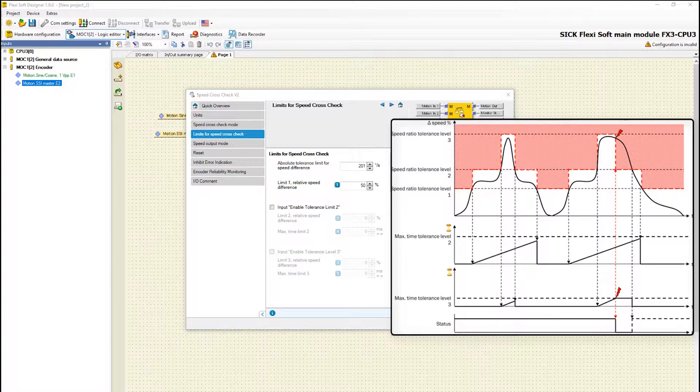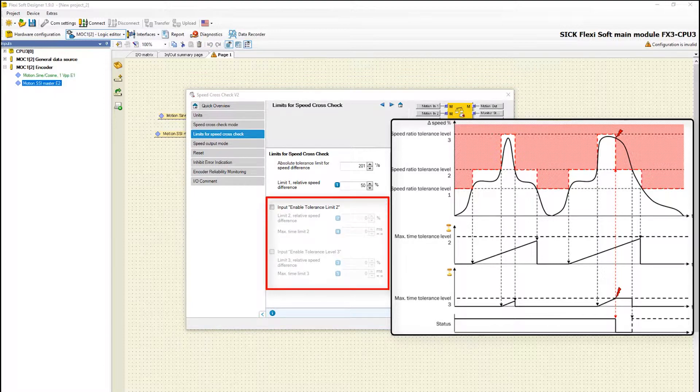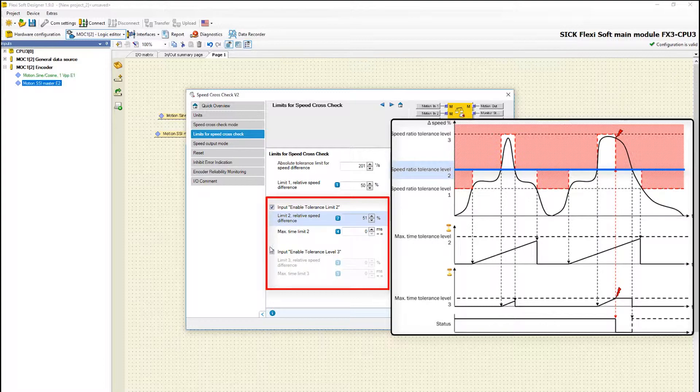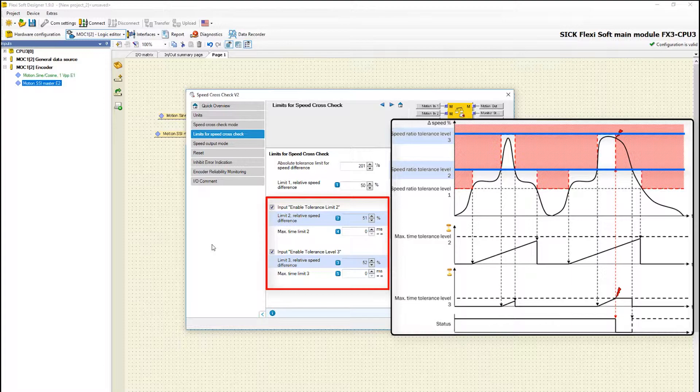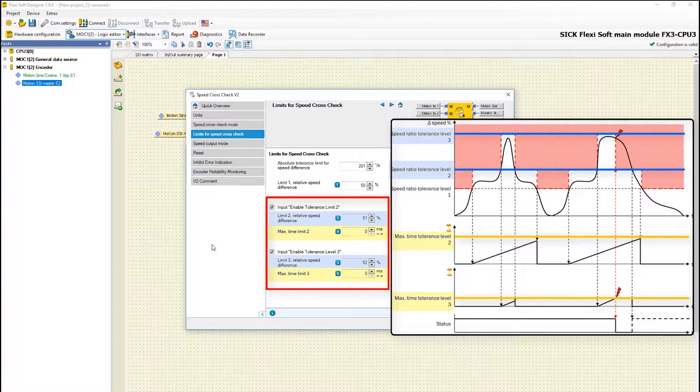Furthermore it is possible to define two additional inputs. This can be used to enable higher speed ratio tolerance levels for a specific time and situation. With the settings in speed ratio tolerance level 2 and 3 you can define a maximum time limit in which the speed ratio tolerance levels should be active.